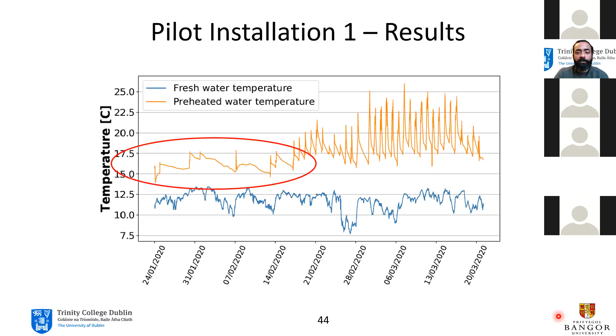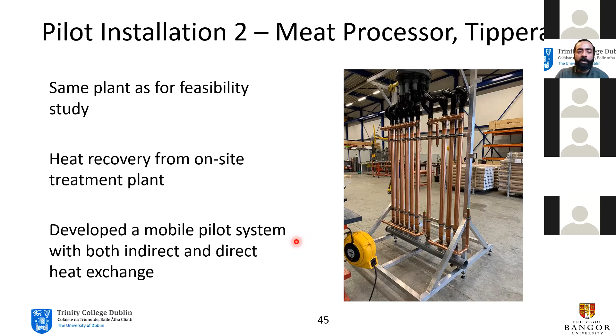There are similar caveats for the second system, where we've struggled as well. We developed a little pilot installation, a portable mobile system, to use at the treatment plant of the meat processor we discussed in Tipperary. We're looking at recovering heat from their treatment plant using a combined system with both shower heat recovery and a heat exchanger attached, serving as an indirect or hybrid system like we discussed. That's what the system looks like fully installed.